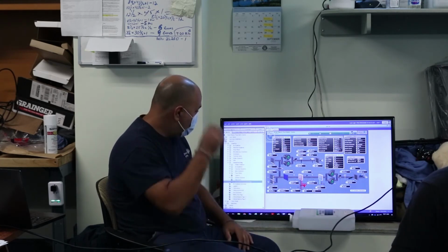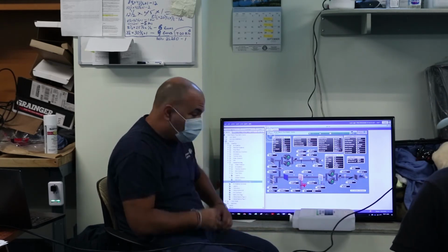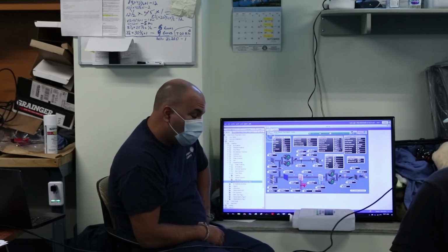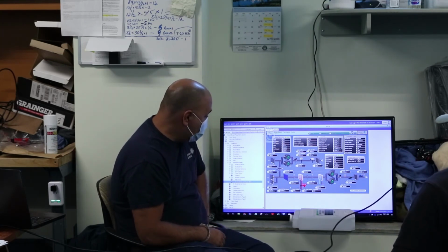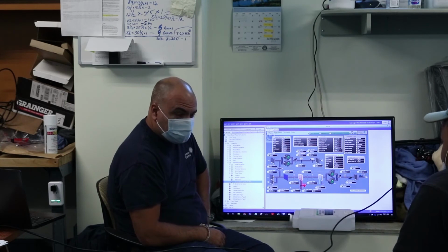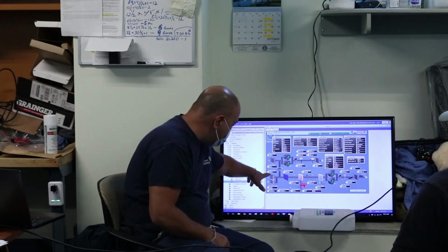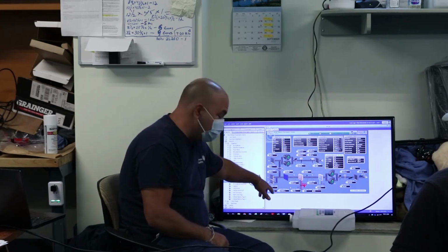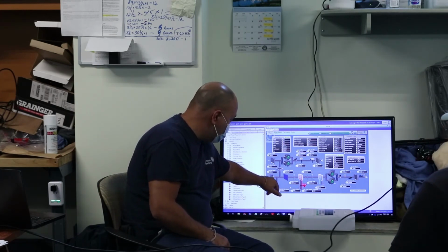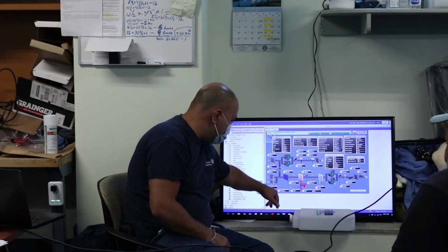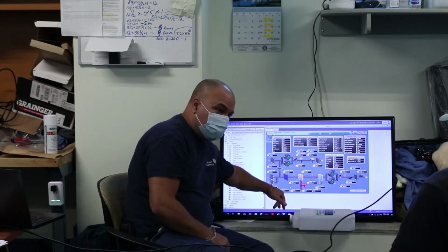So this right now is not even recirculating any air. You're spilling everything because you're an economizer. Yeah. So the economizer is not enough, right? If it was colder outside and the economizer was enough, we'd see that outside air damper back down to the point of making that minimum flow set point.